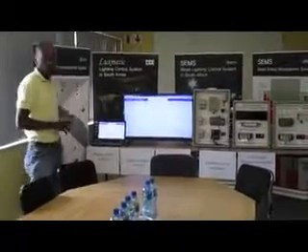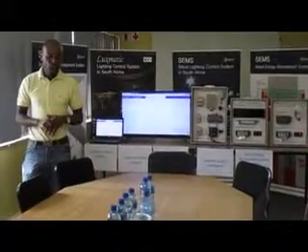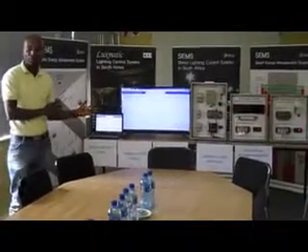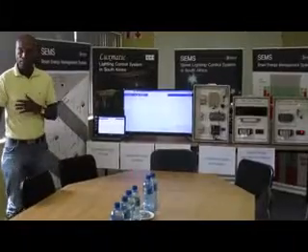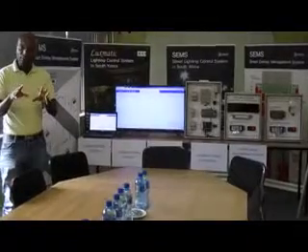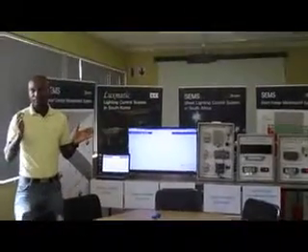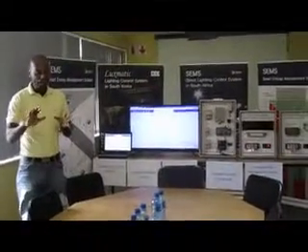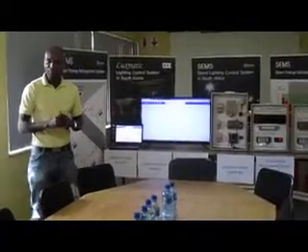Now with what we're implementing here in Bloemfontein, our system has two parts. The first part is software, and the other part is hardware. With the software, we are able to set the system according to our needs, according to the client. When it's sunset, it goes on at 100%, and then maybe around 1 hour after that, it can go to 80%, and around 12 in the morning, it dims automatically to 50%. With that, we can see it's going to save a lot of power.